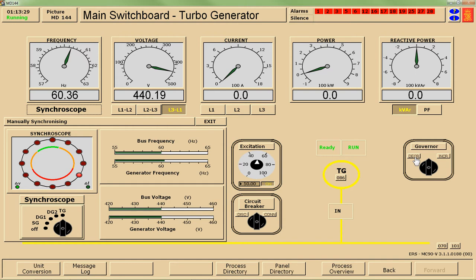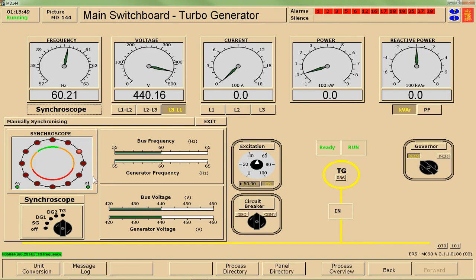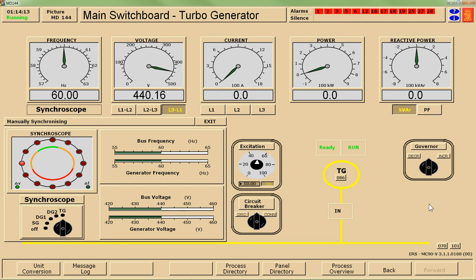So I'll decrease the governor position — we click on and then let go of the button, and click again to turn it off. You can see that as I'm decreasing this governor position, my frequency is dropping, and at some point my light is going to illuminate to tell me my frequency is okay. If I go too far, my light tells me it's no longer okay. So I have a small window where I'm slightly faster than the bus but not too fast — that is my acceptable range. I'm going to increase my governor position until I'm in the acceptable range, and my frequency tells me that it is.